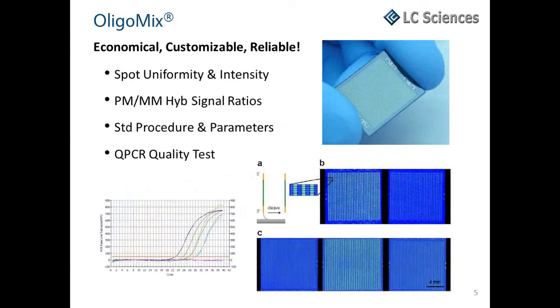We examine hybridization on multiple built-in control sites and analyze the uniformity and intensity of hybridization spots, the cross-chip spot uniformity, and the perfect match and mismatch hybridization signal ratios to assess the quality of OligoMix synthesis. Our QC criteria use standardized procedures and parameters such as signal intensity, signal covariance, and the perfect match and mismatch ratio. Additionally, we can perform a QPCR quality test on specified sequences within the mix.